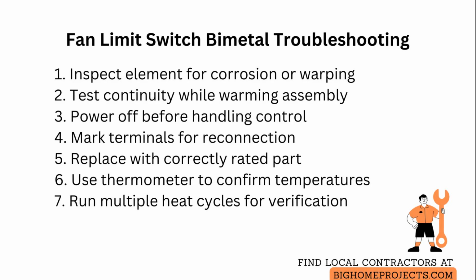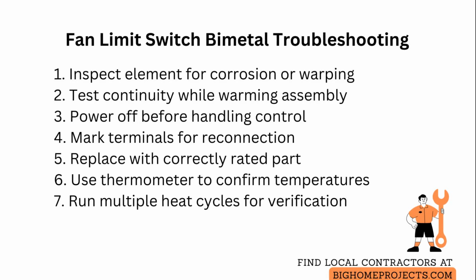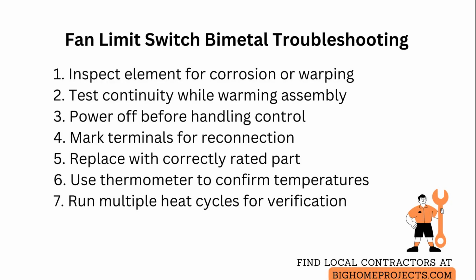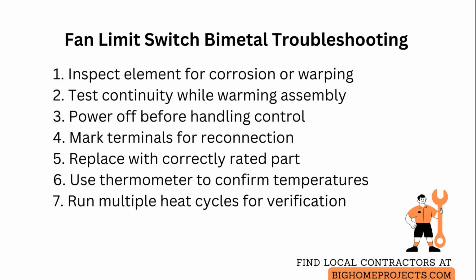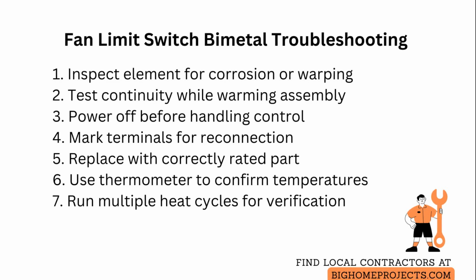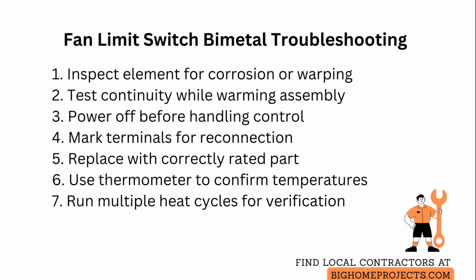When replacing, set the control per manufacturer instructions using a reliable oven thermometer at the heat exchanger exit or a contact thermometer on the control body to confirm the cut-in and cut-out temperatures. Avoid attempting frequent dial adjustments or temporary mechanical tweaks because those mask the loss of material properties in the bimetal and create unsafe operating conditions.